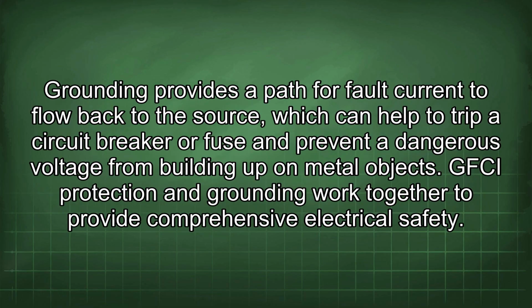It's also important to note that GFCI protection is not a substitute for proper grounding. Grounding provides a path for fault current to flow back to the source, which can help to trip a circuit breaker or fuse and prevent a dangerous voltage from building up on metal objects. GFCI protection and grounding work together to provide comprehensive electrical safety.